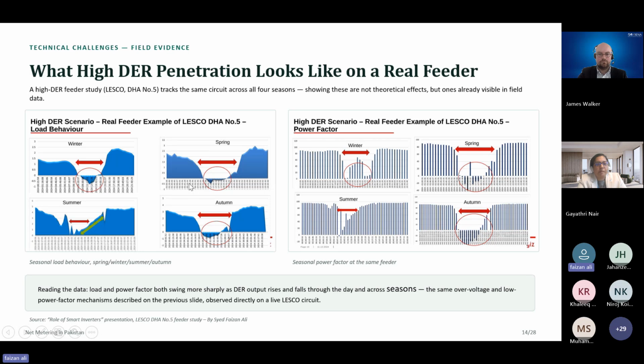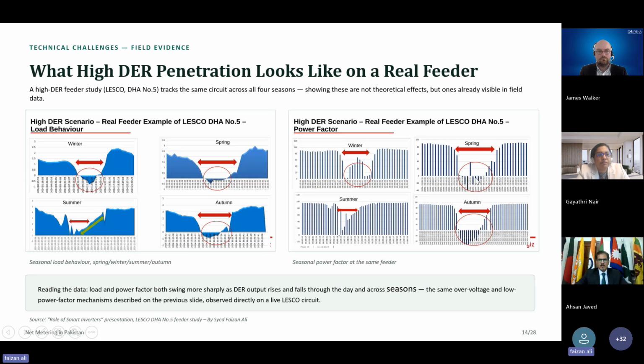And on the right side, we see that whenever there is this reverse power flow, the power factor drops as well. It drops to the range of 0.6. And in the spring season, when there is maximum reverse power flow, we see it goes very low, almost zeros out. So this is something of concern.